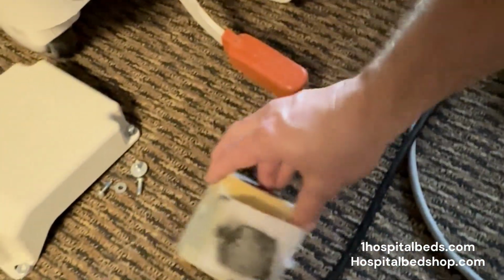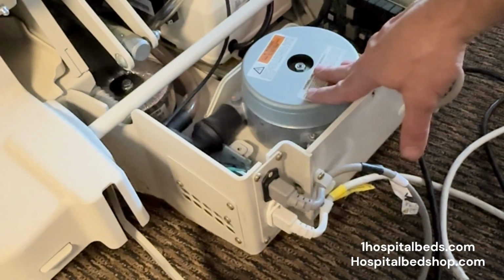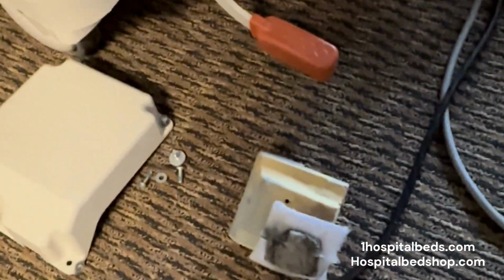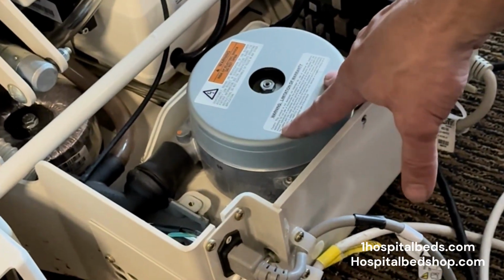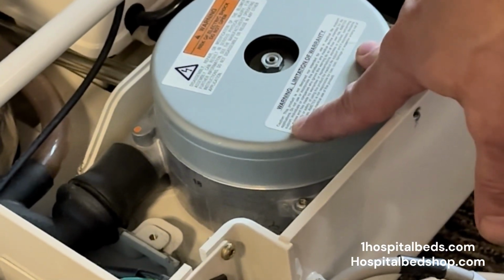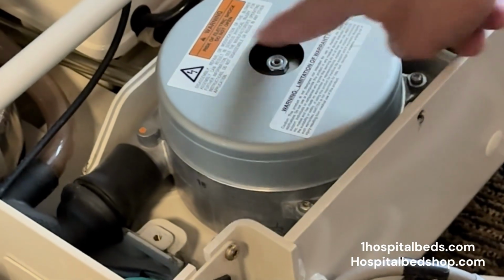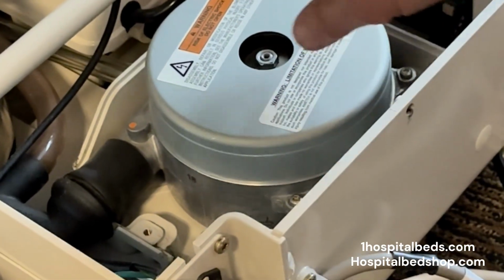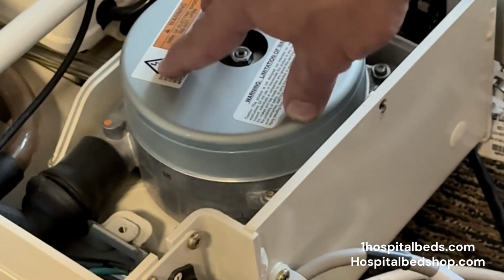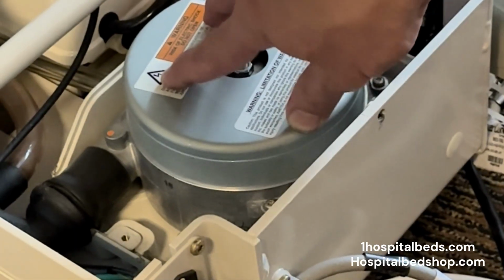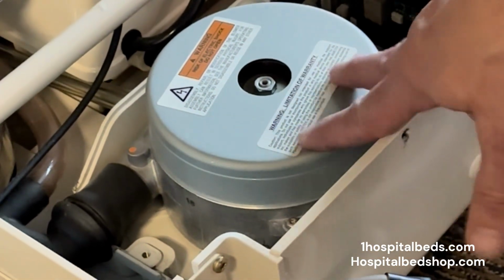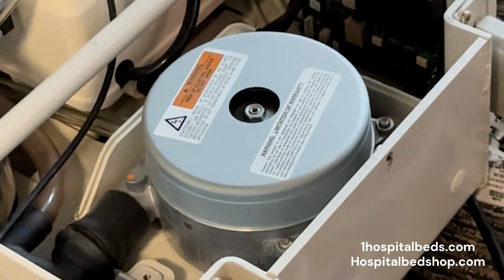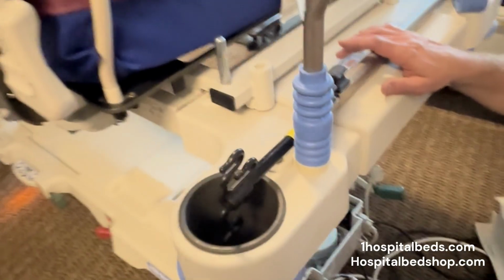That's your intake system, right there. And these have to be taken off. The cover has to be taken completely off in order to service this unit. If you don't take this cover off and clean that filter, eventually this blower will begin to scream, audibly, you'll be able to hear it. As it gets hotter and hotter, it overheats the bearings inside the blower, and eventually the blower will quit working due to excessive heat. So when that happens, the entire air system will eventually go down, and that gets very expensive.